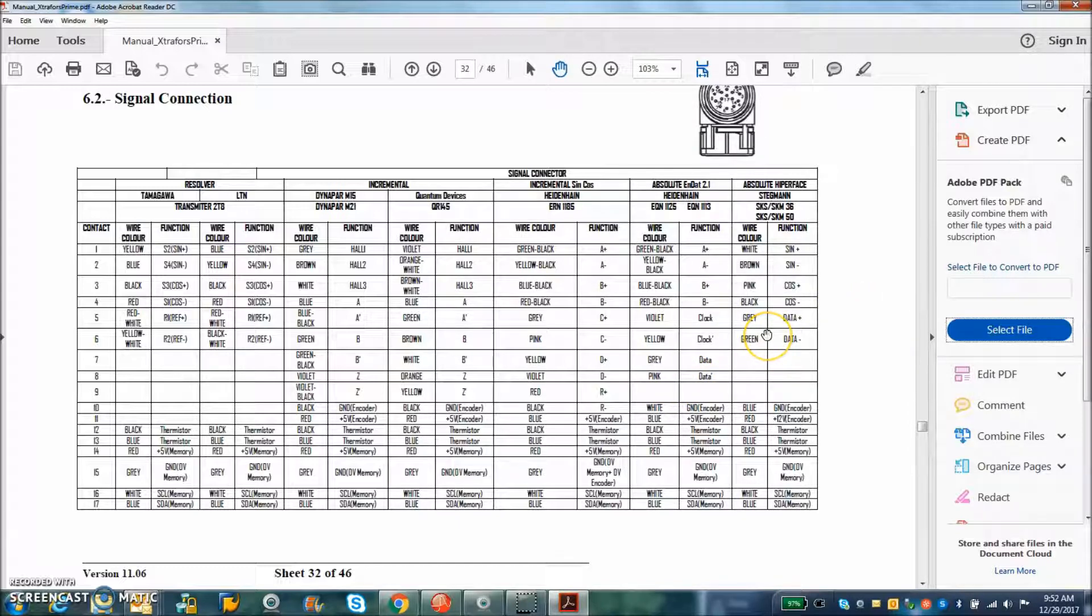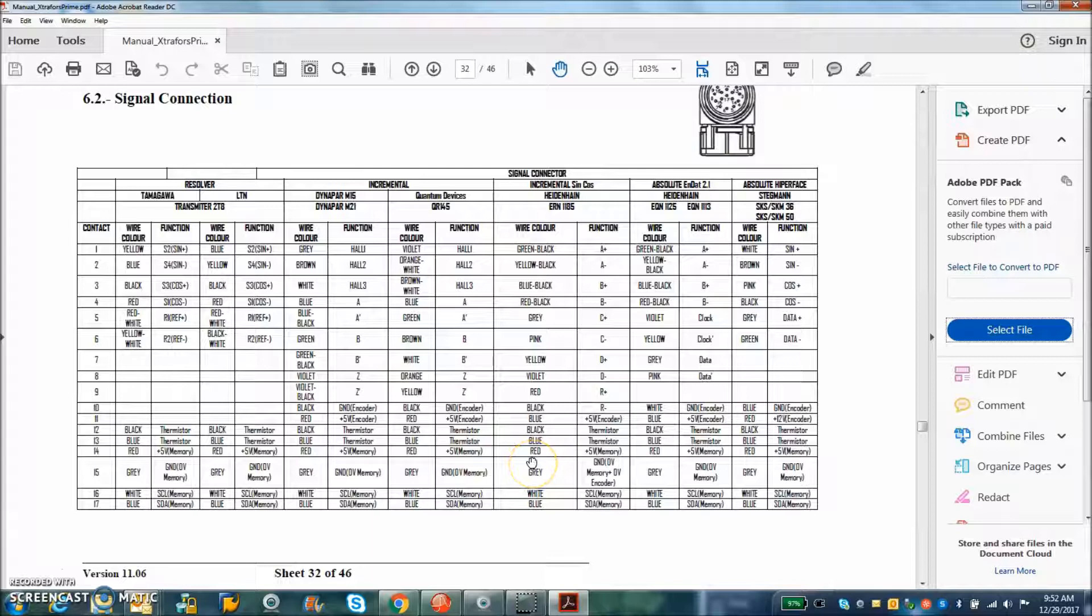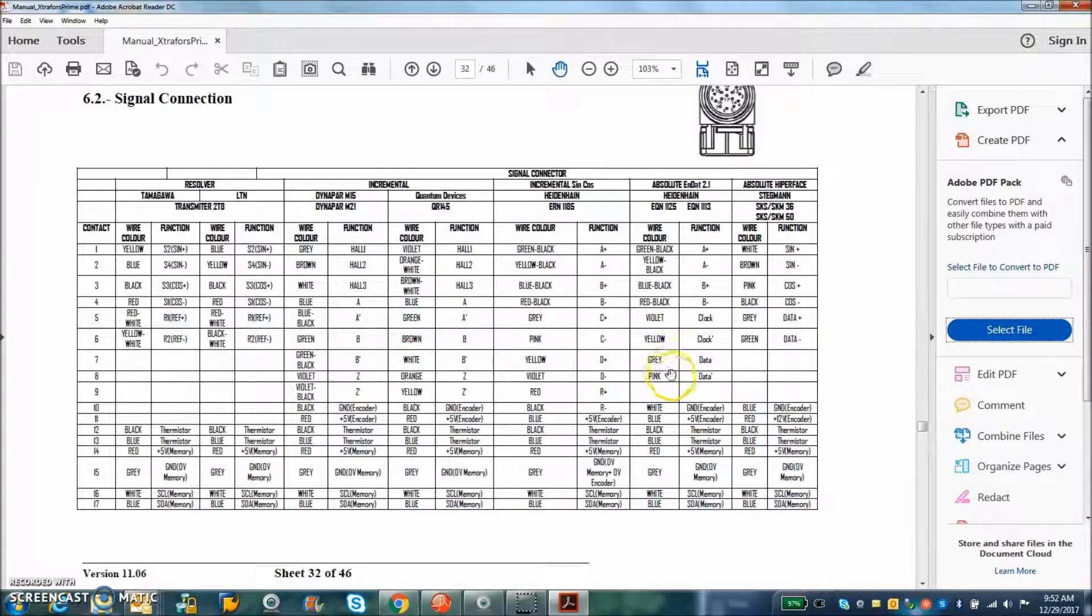I don't like to talk about Hiperface because the voltage is normally required. See the 12 volt here for the encoder. And everybody else is 5 volt. So I'd say stay away from the Hiperface and go with the EnDat 2.2.